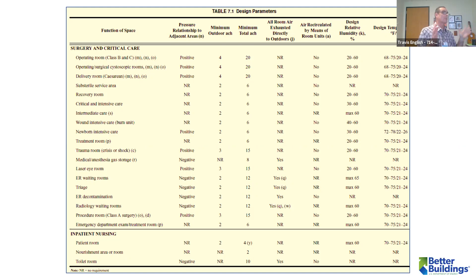That is worthy of criticism. You could criticize us for that. But another thing ASHRAE doesn't always advertise is that they've actually looked at the research behind those air change rules and found it to be quite poor. A study on ASHRAE letterhead from last year shows that about 75-95% of our healthcare ventilation air change requirements have no evidence basis, no clinical basis, no rational basis. So there's not a strong case for voluntary adoption of a very energy intense standard.